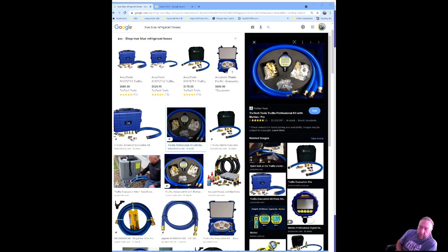What they say is even if you have a very large pump, your vacuum process is very much impeded by the diameter of the hoses that you use, especially if you go for the gauges. Whereas here it's like a direct line to your system, and because of the diameter, it speeds up the process considerably. They're very fast.